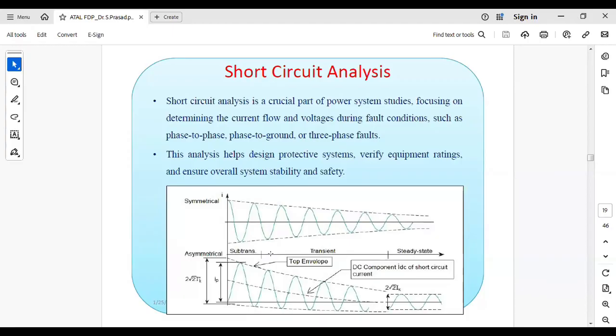So we have to go for short circuit analysis: three-phase short circuit, line to ground fault, double line to ground fault, and line to line fault. All these cases you have to consider, and you have to analyze the maximum short circuit current and the minimum short circuit current.